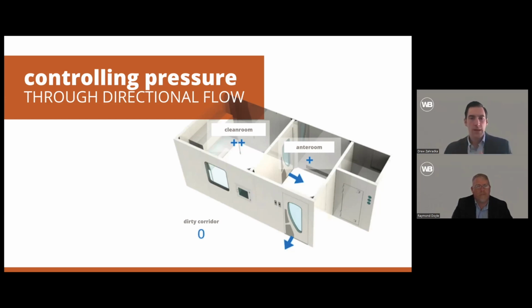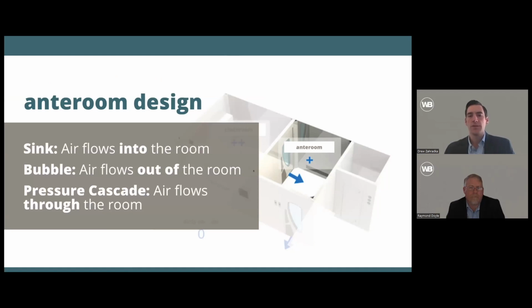Some clean rooms, which is what we've got up here, as you can see, have an anteroom, which is an airlock that is used as another layer or level of separation from your dirty corridor, or where common foot traffic is. So in order to get into the cleanest space, you have to go through another room or level of different pressurization. Your anterooms can be designed as sinks, bubbles, or they can have a standard pressure cascade.